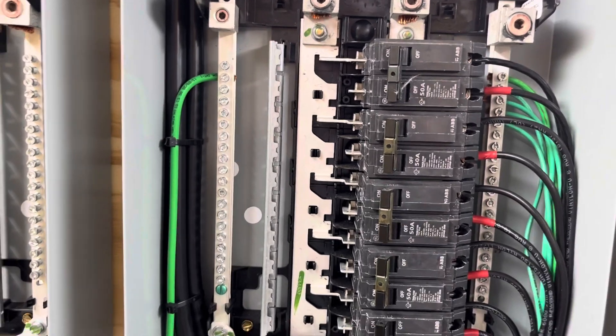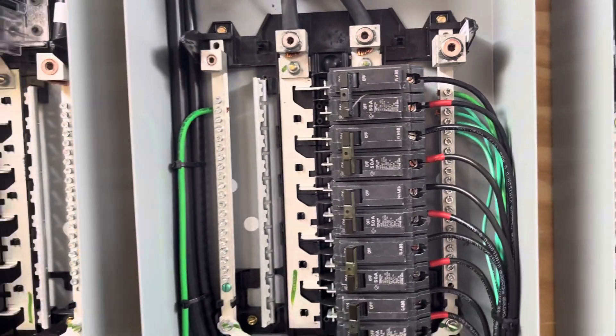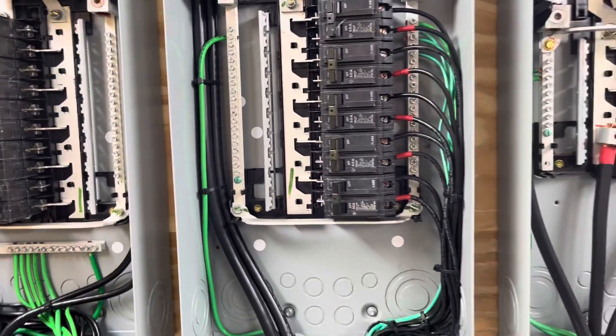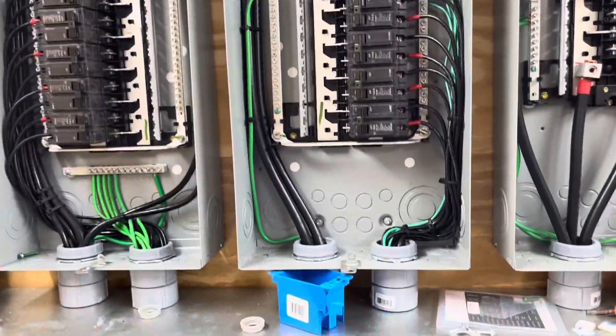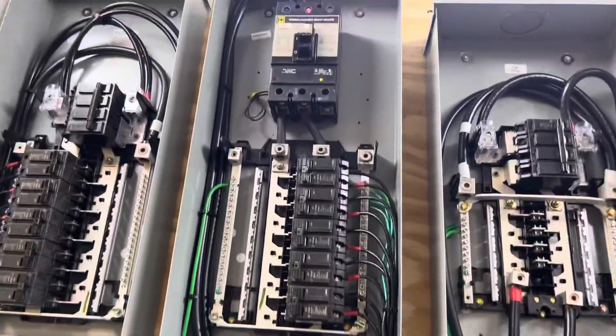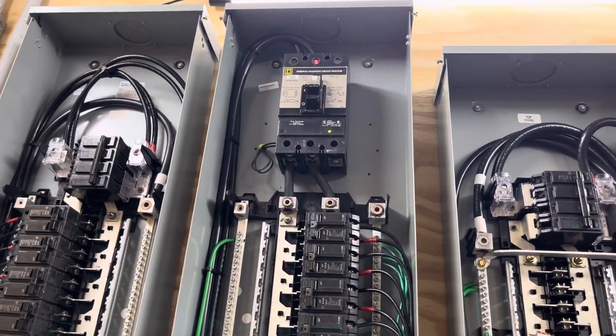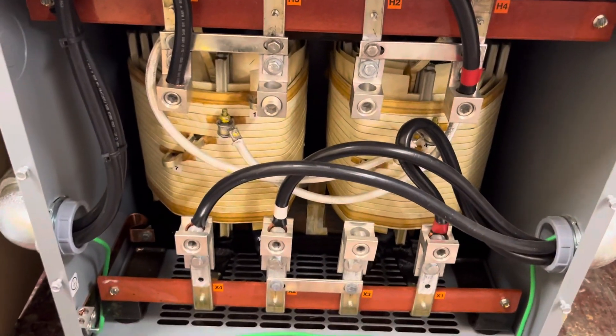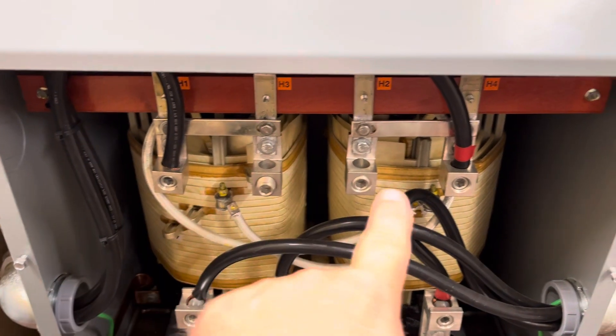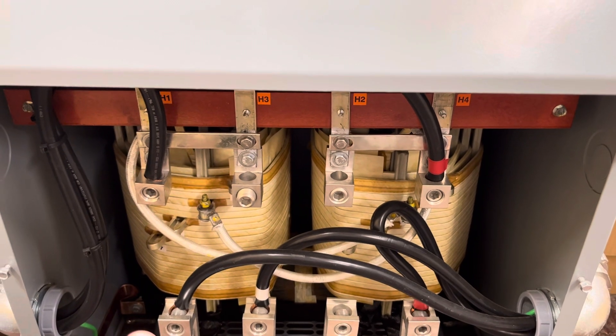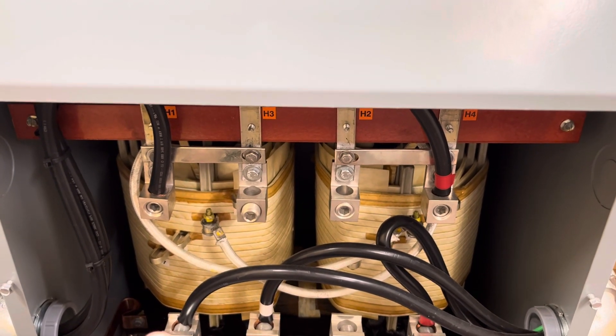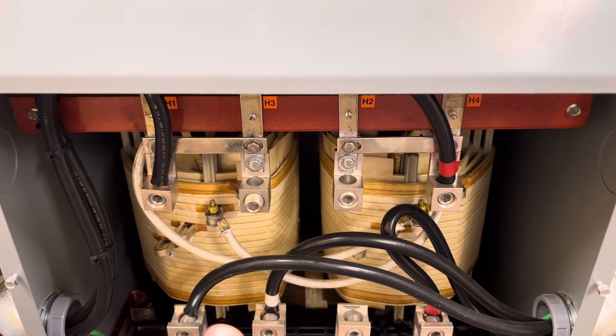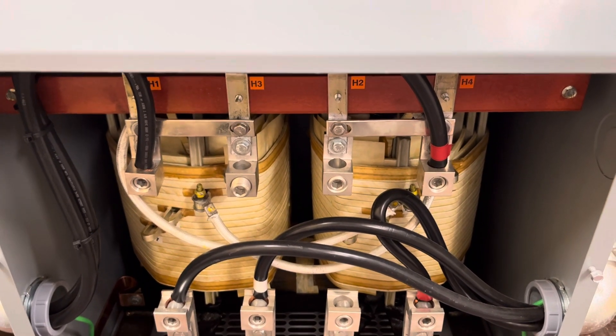So to remedy all that and get me the neutral that I have to have for my house, I come through an isolation transformer. That breaker right there, out of the top, it back feeds out of the top and comes into this transformer to the primary side. This is the primary side right here. This is a 50 kVA 240 slash 480 volt slash 120-240 volt transformer.